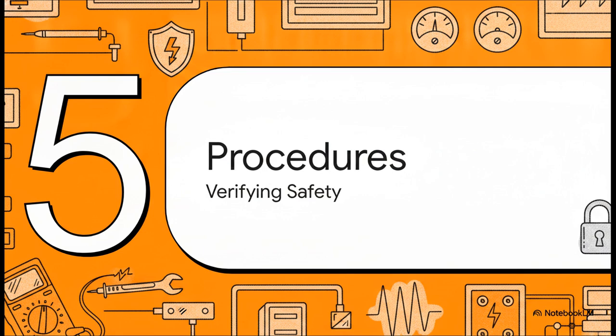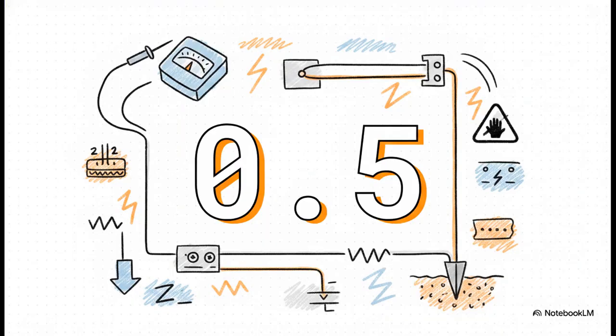Okay, final section. Part 5. Step-by-step procedures. Let's actually verify that safety. 0.5, half an ohm. When you are testing the main earthing conductor, and I'm talking specifically about testing between the disconnected NEN link at the neutral bar and the main earthing conductor down at the earth electrode, the resistance must never, ever exceed 0.5 ohms. You isolate it, you check your ohm meter, you test across that path, and you look for that crucial reading. If it's over 0.5 ohms, your earth path has too much resistance and it simply cannot be considered safe.